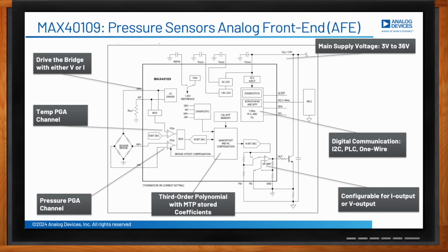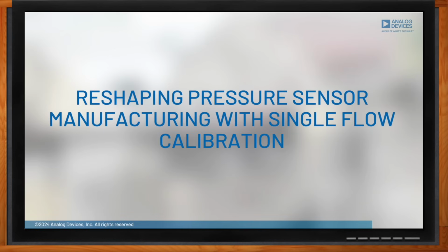Okay, so what are the benefits of this ADI solution for pressure sensing applications? There are several benefits provided by the MAX40109. The most important one is that it reshapes the way pressure sensor manufacturing is done by reducing it to a single flow calibration. The second most important benefit is that it enables temperature to be measured directly from the resistive sensor bridge, thus eliminating the need for dedicated temp sensors. Finally, the solution is very tiny to fit in tiny systems like pressure sensor transmitters.